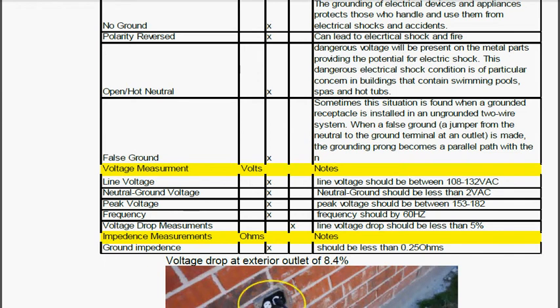I have to tell you, the electrical circuitry in this house is the best I've tested - it really was good. I found one outlet with a voltage drop of 8.4%, but all the others were literally less than 5%, some 3 and 4%. It was reassuring for me, because sometimes I wonder about my equipment when I keep getting a voltage drop and think, is it really a drop or is it the equipment - do I need to recalibrate? So I do, and I get the same reading, and then I think I've got to find somewhere with less than 5%. I found it - I found the house. It's good.